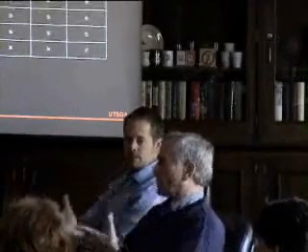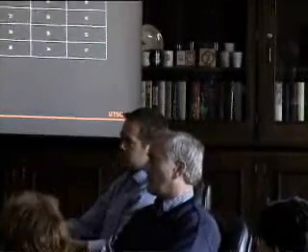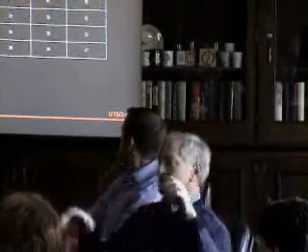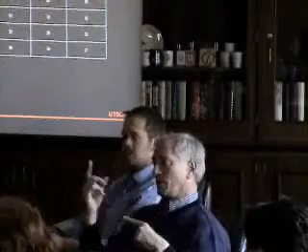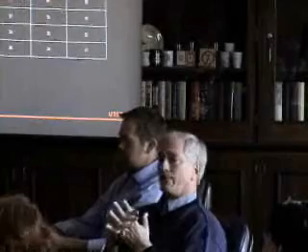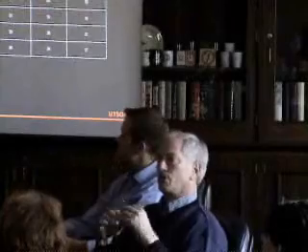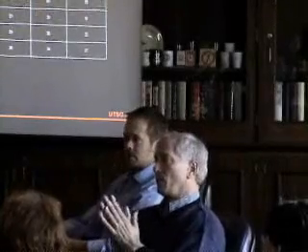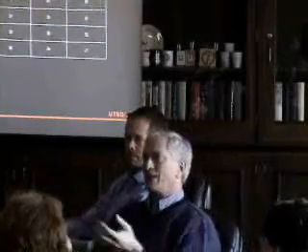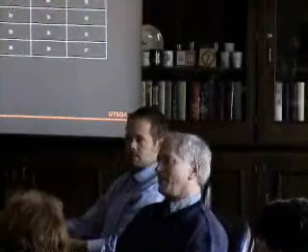And so that kind of pressure available at all times outstrips the benefits that we could otherwise calculate. If in the future we grow new edge cities and we think about this ahead of time with reuse systems or non-potable systems and so on, we can learn a lot from history. Older cities have dual systems, like a lot of Chicago has a dual system in the industrial areas where fire flow demand is met through fire pipes. And they use lake water for fire demand in the industrial areas. They don't treat it. They don't keep it under that same system of quality municipal potable water.